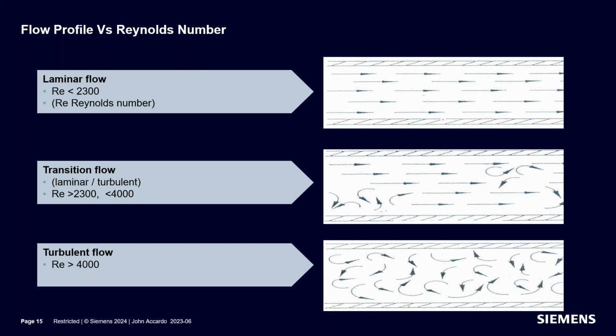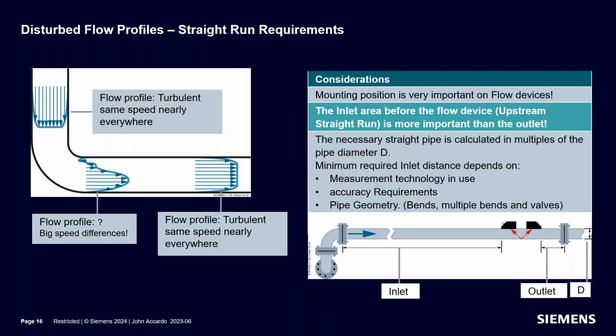But what would be ridiculous is if you put in the wrong viscosity number and the meter thought you were laminar and you were really turbulent, or vice versa. Then you could see upwards of an 18% flow reading error. Okay, so knowing your viscosity is important. Again, when you pick a liquid, it plugs in a default viscosity. But if you have an application where viscosity varies, well, you need to know what that is, and we do address that. And I know I'm really taking a long time here, so I'm going to try to move it along as quickly as I can.